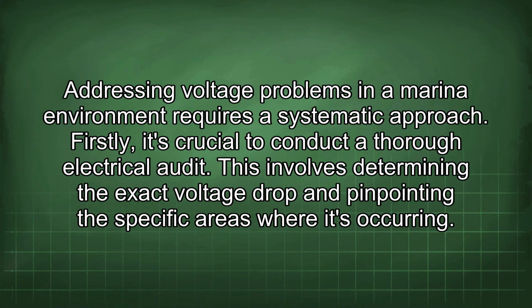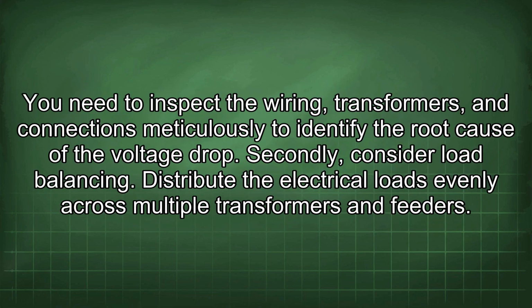Addressing voltage problems in a marina environment requires a systematic approach. Firstly, it's crucial to conduct a thorough electrical audit. This involves determining the exact voltage drop and pinpointing the specific areas where it's occurring. You need to inspect the wiring, transformers, and connections meticulously to identify the root cause of the voltage drop.